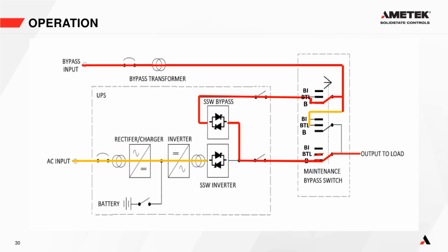So therefore, there is going to be a point where the power on this line here is going to be the same as the power on this line here. And if we make those both bypass by pressing this bypass static switch button, then we are paralleling bypass and bypass together. And therefore, the waveforms are always going to be perfectly in sync because they are the same. So you can never have an issue. So whenever you move the physical maintenance bypass switch from normal to bypass to load, you always want to press the static switch bypass to load button. And all of our procedures on our UPSs tell you that, okay?